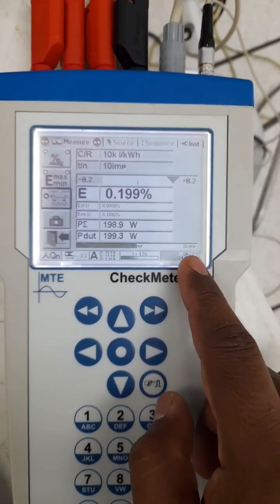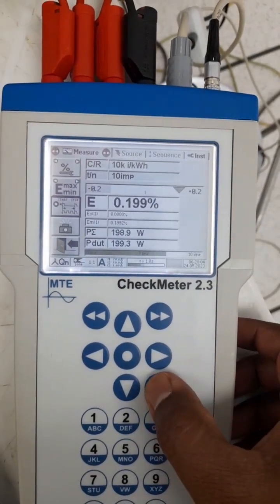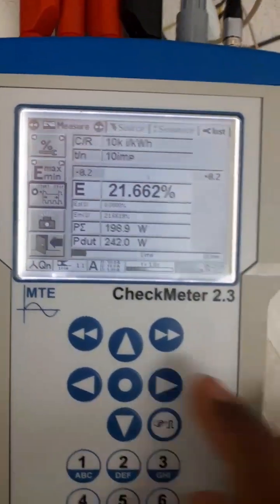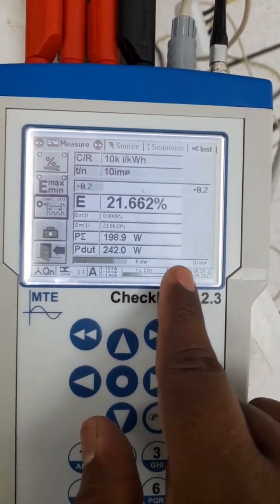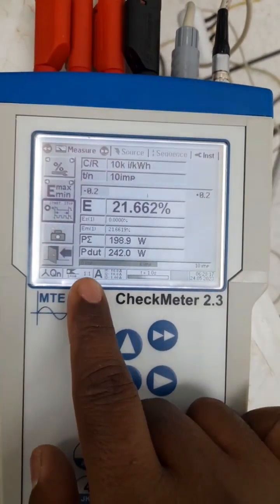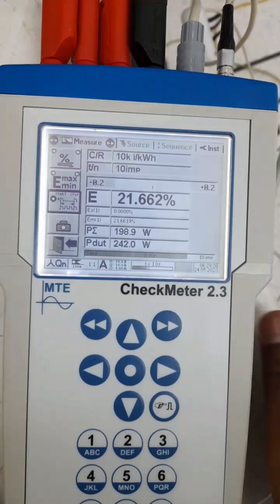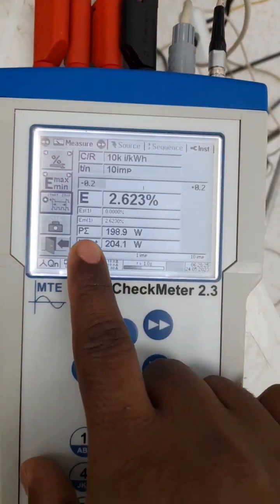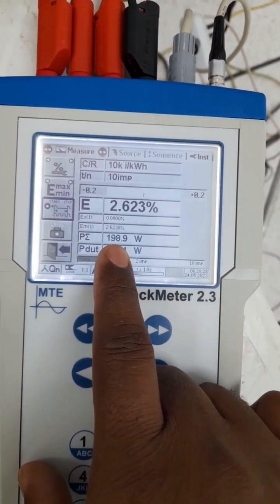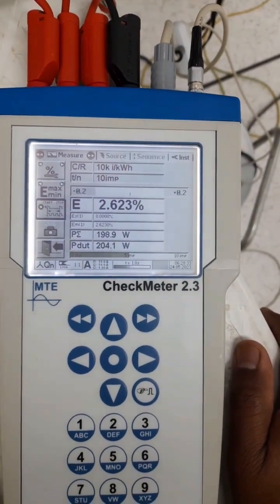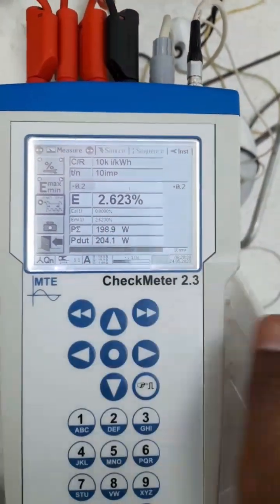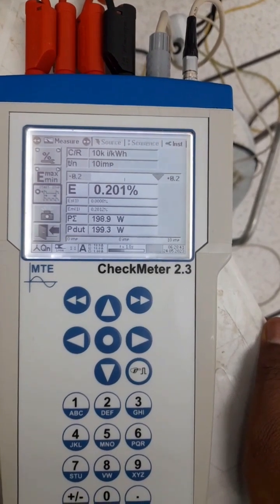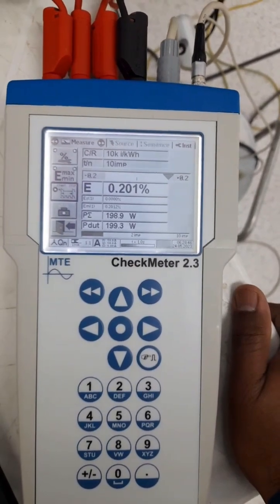My error now is 0.19. I'm going to press again. It started freshly. Now the pulse started to count. If you check here, the pulse 2, and once it's counted the 10 pulse completely, this P pulse out will change. Based on this value, your error will be calculated. The first one is active energy, this is calculated based on the input voltage and current, 198.9. Actually, if your CT polarity is reversed, it will completely disrupt this value. Now it's done. My error is 0.2. We will wait for two more readings.